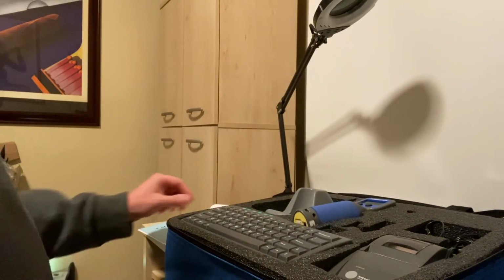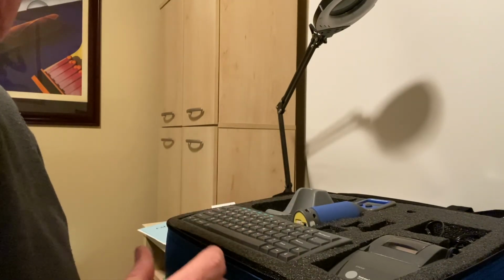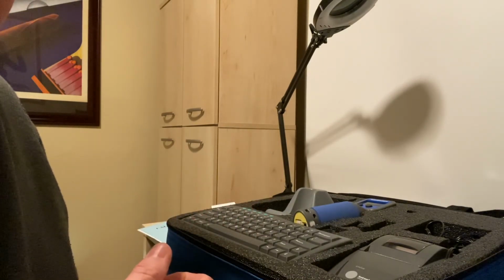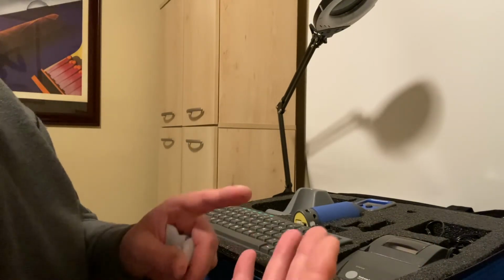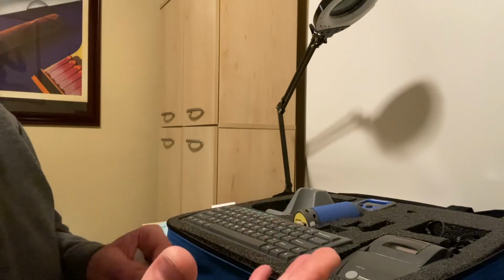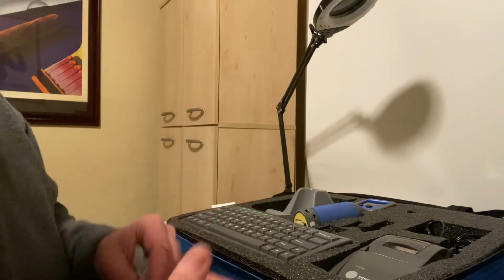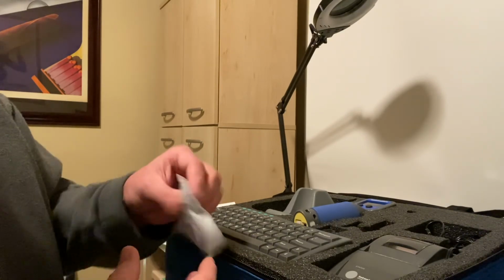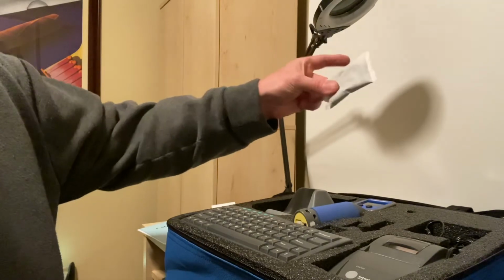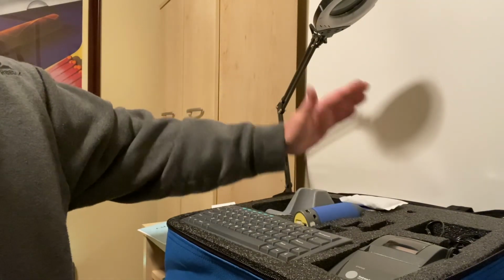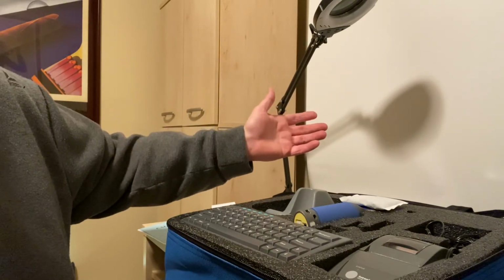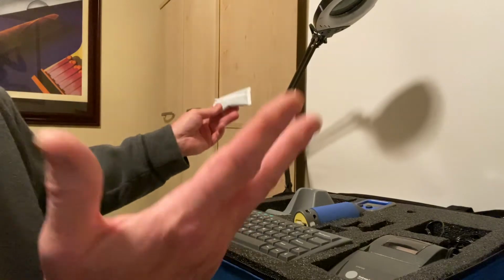Now, when I first tried to do this video, I had my house set at like 68 degrees. So when I went to do the calibration, I got an error that said temperature too low. And that happened to me when I first got it. It was wintertime, and I had to call Alco Pro, and I found out that this machine has to stay in a climate between 71 and 85 degrees, or you'll get that error, too low, too high, when you do the calibration. So what I did was, I kept some hand warmers, and I just placed it on the top right there. I closed it up for 15 minutes and then opened it back up, and it was on the money.